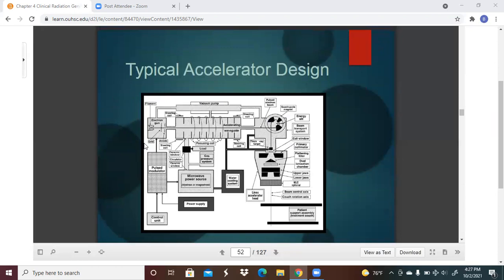So here is one design that has a lot of these components already in there. Grid, anode, you've got your electron gun, vacuum pump, steering coils, accelerating waveguide, the pulsed electron beam, and then the quadrupole magnet, which turns it 270 degrees down this way. Then it comes to the exit window. You've got a primary collimator, a dual ionization chamber, the flattening filter, upper and lower jaws.